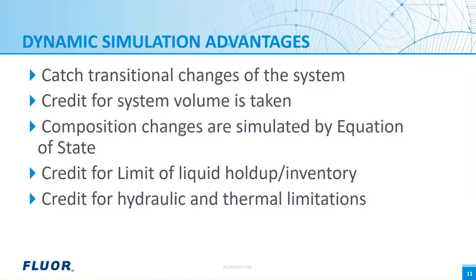Dynamic simulation is a rigorous modeling method with detailed system configurations. It has the advantage of capturing dynamic changes such as compositional change and transient changes. It takes credit for system volume and limited liquid holdup, as well as system hydraulic limitations such as pump head, static head, and pressure losses during relief. It also accounts for thermal limitations — for example, the increased log mean temperature difference (LMTD) for overhead cooling and decreased LMTD for the reboiler. As a result, relief loads predicted by dynamic simulation are less conservative but more accurate, and can save millions for the project.